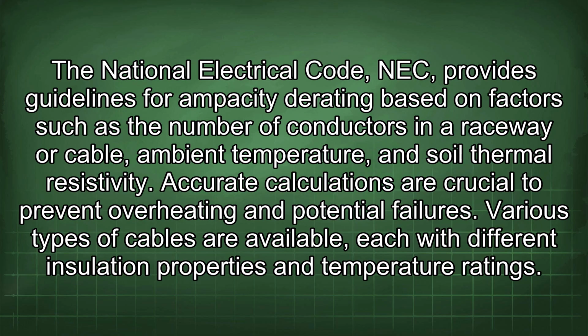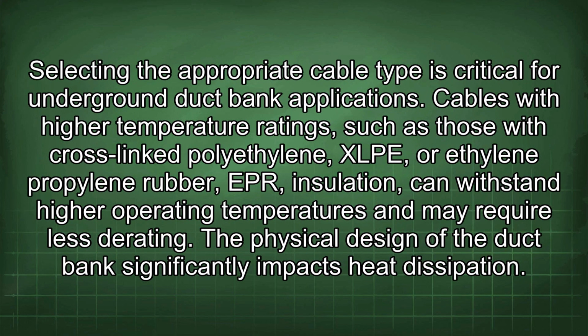Various types of cables are available, each with different insulation properties and temperature ratings. Selecting the appropriate cable type is critical for underground duct bank applications. Cables with higher temperature ratings, such as those with cross-linked polyethylene (XLPE) or ethylene propylene rubber (EPR) insulation, can withstand higher operating temperatures and may require less derating.